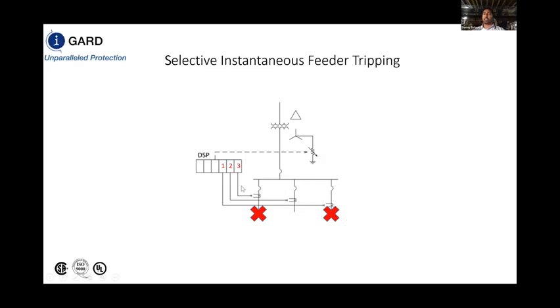As a result, if we didn't have our DSP system here, the instantaneous function of these 2 breakers would effectively trip out, and we'd lose power to both of these feeds. But with our DSP system, we can assign priorities to each of the feeders based on the criticality of those feeds and trip the lower priority feeder in favor of keeping the higher priority feeder in play. So only tripping one out of the 2 and reverting us back to the first fault condition, where the remaining fault will now circulate back through to the NGR to be limited.